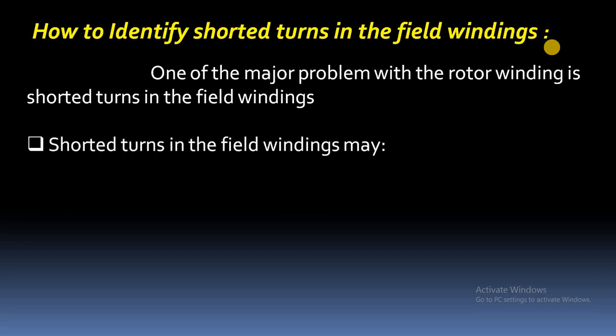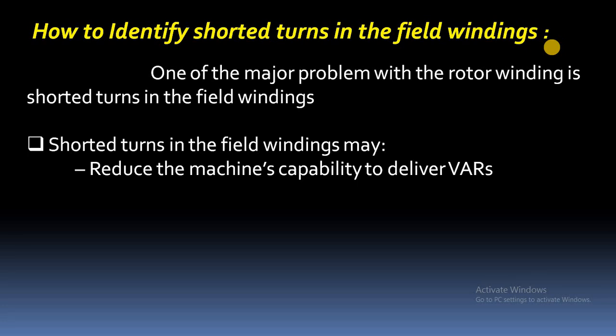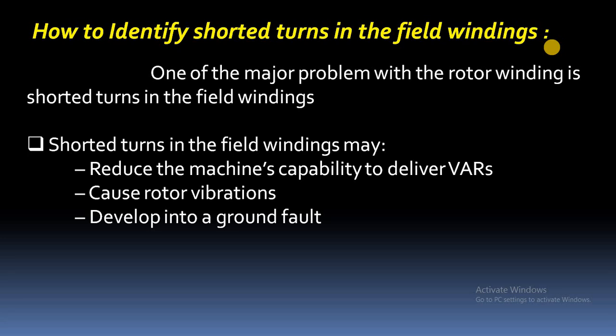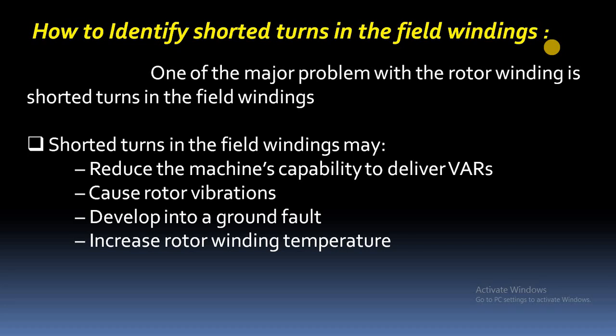Because of these shorted windings, what are the disadvantages? The shorted windings in the field winding will reduce the machine's capability to deliver the rated VARs, because the rated flux will decrease. These shorted turns will also generate non-uniform air gap flux density, which results in rotor vibrations. Furthermore, these shorted turns can develop into a ground fault leading to a rotor earth fault, and they will increase the rotor winding temperature by reducing rotor impedance, causing the rotor winding to draw excessive current and generate more heat.